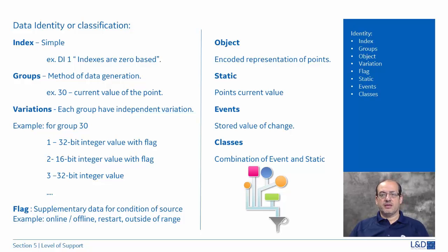So let's take an example. If I say the information from the field is showing that the breaker is open, right? Or the status, the digital input value, is 0. Is it 0 because it's really open? Or is it 0 because the monitoring point is offline? So that's why this extra data is important to us as monitors of the SCADA system to take the right action, that we're not just looking at the value of the data, but we're also looking at the status or the quality information of that data that we're receiving.